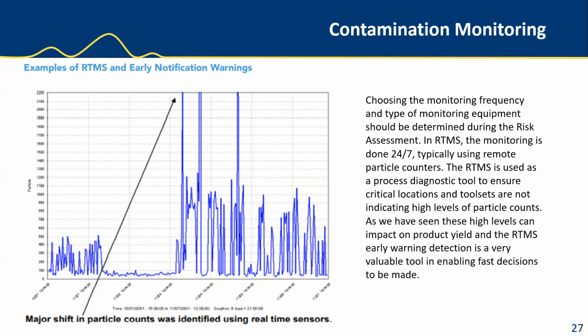If the surrounding environment did not have a particle counter monitoring it, the issue could have been a major one. The technician would have reported high concentration on the wafers and would be looking at previous processes to identify the failure. That would have been pretty futile, as the origin of contamination was coming from the room environment where the DMA tool was located.